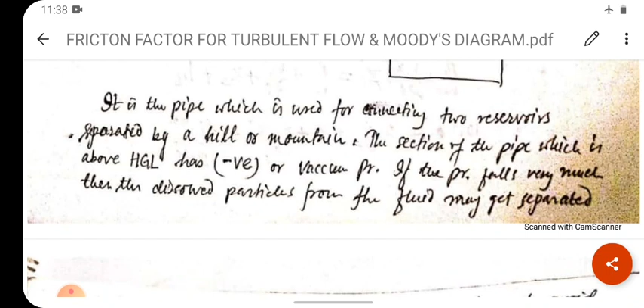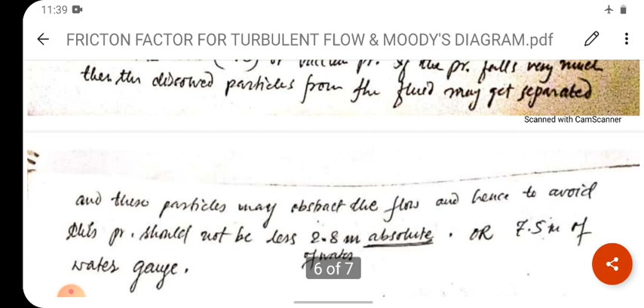If the pressure falls very much, then the dissolved particles from the fluid may get separated and hence the particles may obstruct the flow. Clear? And hence to avoid this, pressure should not be less than 2.8 meter of water. The absolute pressure should not be less than this, it must remain at least that. 2.8 meter of water is absolute, or 7.5 meter of water gauge. So we'll solve one problem. This will be more clear to you.